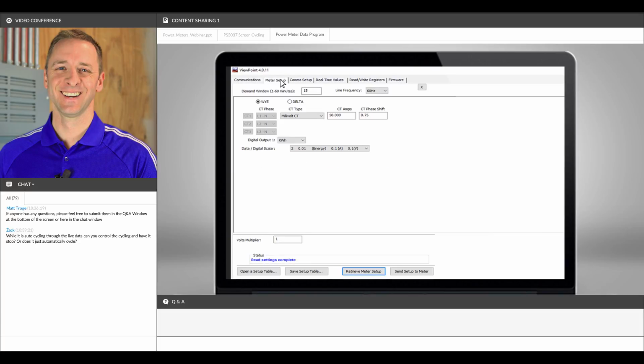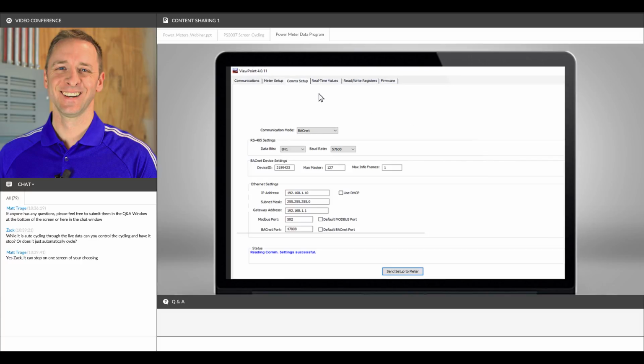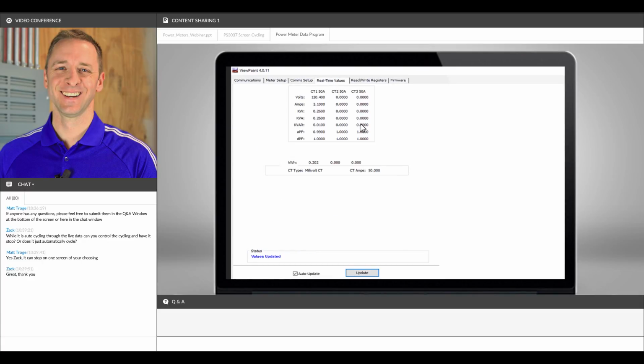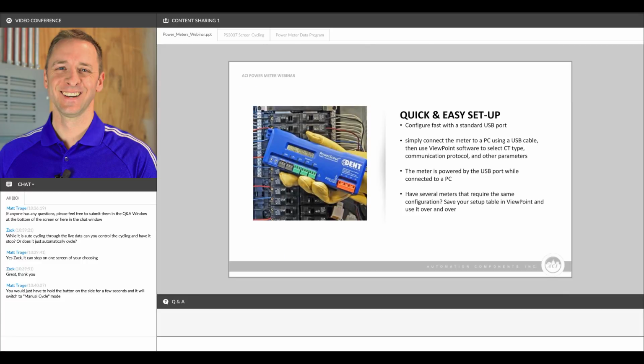A neat feature about the Viewpoint software is that if you're setting up multiple devices, so say you want to monitor multiple pieces of equipment in a single building, or you have a set list of parameters that you want to measure across numerous devices, you can save the configurations in the Viewpoint software and then download those into each device separately instead of having to reconfigure each device during the setup process. And the Viewpoint software is available for download on our website. So if you'd like to take a look at it and see for yourself how easy it is to use before purchasing or testing one of these power meters, feel free to reach out and we can get you that link to where you can download the Viewpoint software.